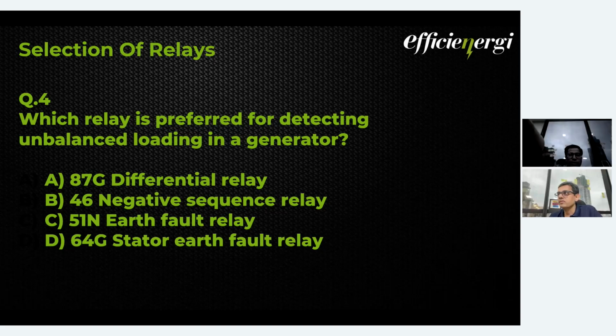Okay, what is the answer for this as per poll? A and B are the most voted. Okay, so basically 51 is earth fault, right? Yes. I was thinking unbalanced loading means you may feel there is a kind of earth fault. Okay, so the answer is basically B. It's a negative sequence relay that we are using for unbalanced loading.